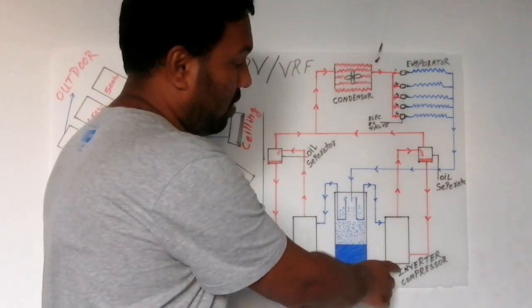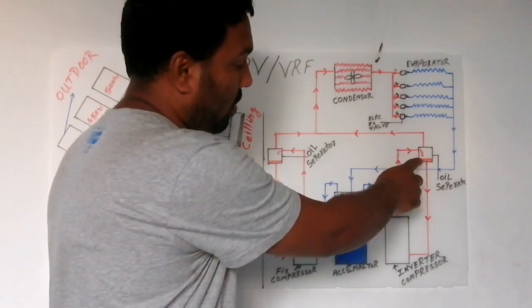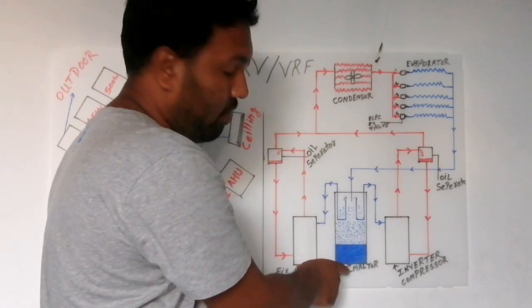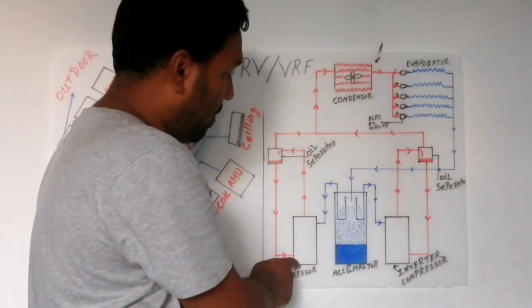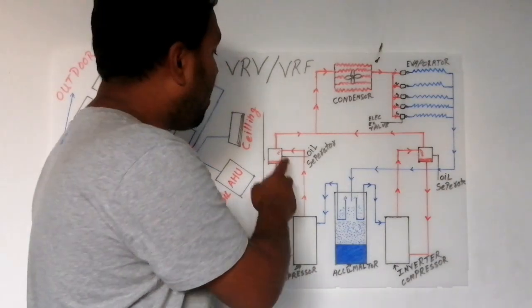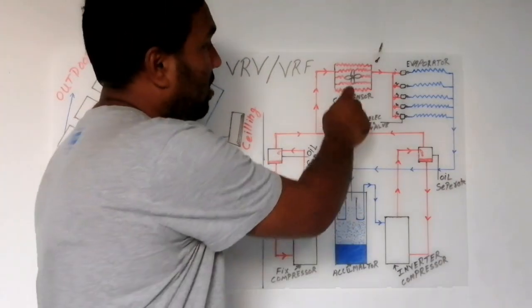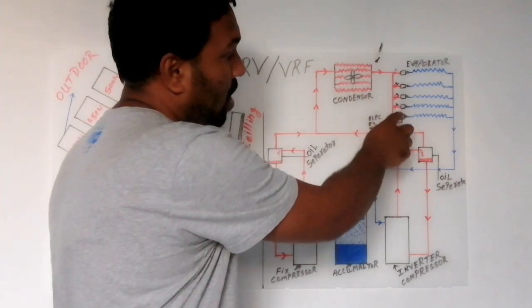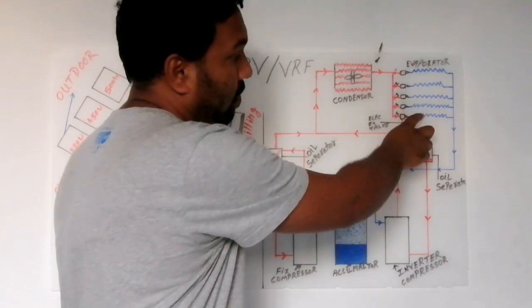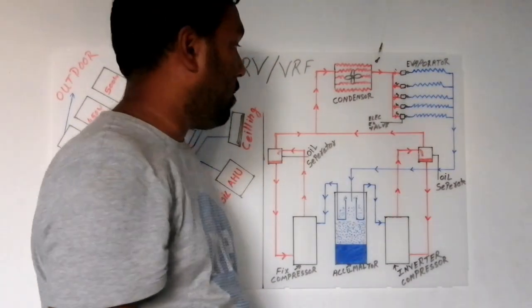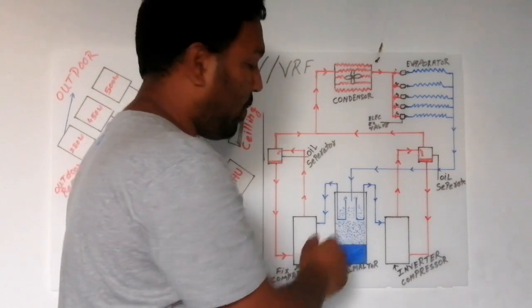This is the inverter compressor. For one inverter compressor, we have one oil separator, and in the center we have the accumulator. And this is the fixed compressor, and for the fixed compressor we have one separate oil separator. And this is our condenser coil, and these are the 5 expansion valves, and these are the 5 evaporator coils, meaning indoor units.